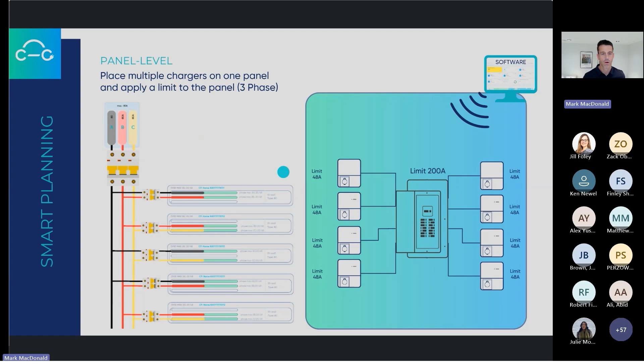Where this becomes even more valuable from a design, engineering, and cost to deploy perspective is when we do a multi-level load share. So now we're actually going to protect the panel or a group of panels. This is a pretty common layout for a multi-unit residential building. I've got my main switchboard here. I've got a secondary transformer fed from that main switchboard. Then I have multiple panels or a dedicated EV transformer and dedicated EV panels feeding all of the parking spots in that building. Now I can put a hard cap on my 4-to-1 load share on the breakers on each panel, but I can also protect the secondary transformer.